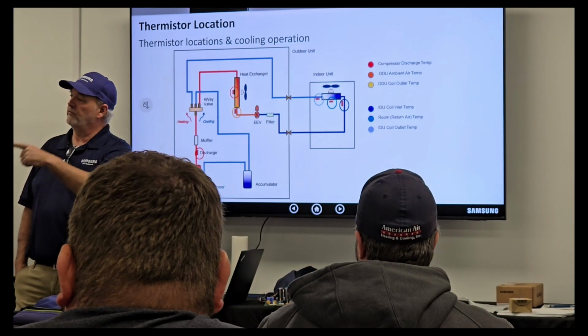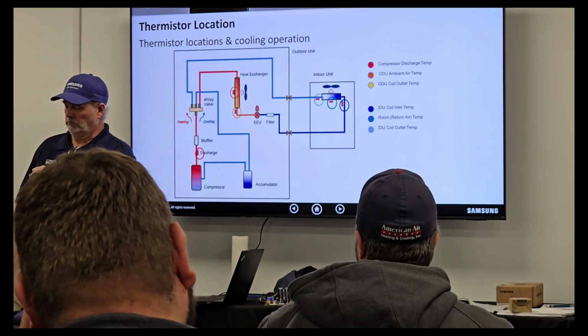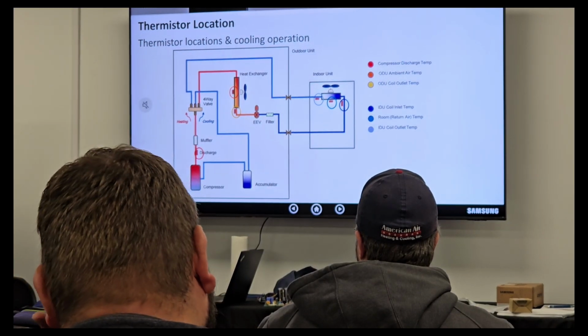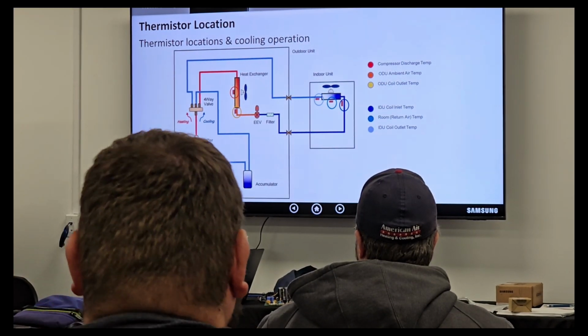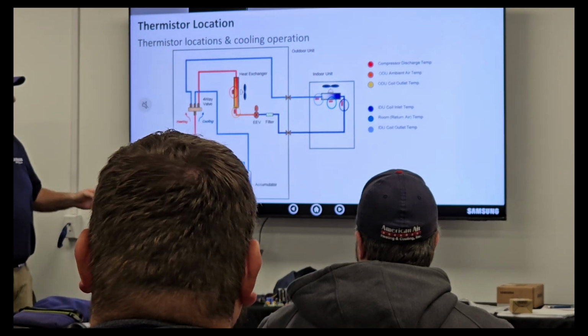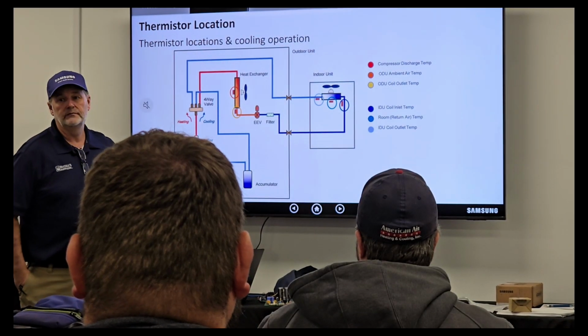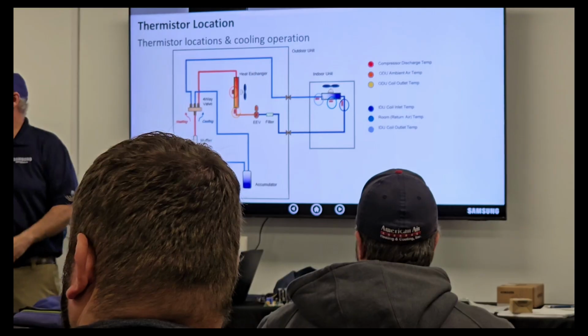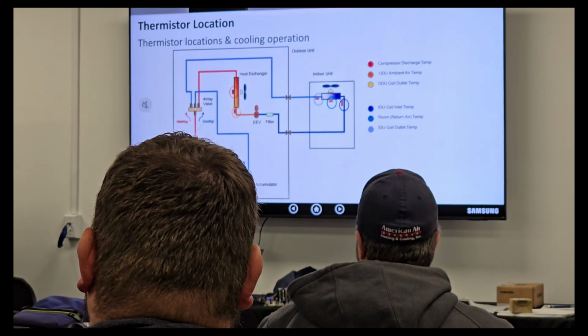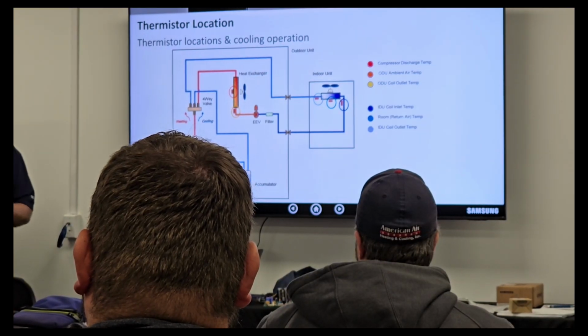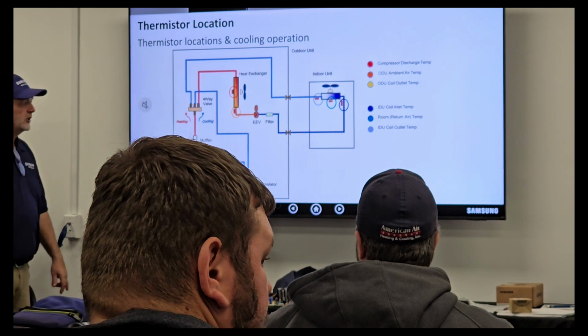From there, all that debris is gonna go straight to the four-way valve, straight to my EEV. Does it cause any problems? Maybe not at first, but what happens to that debris when it gets to that compressor? It destroys the compressor inside. Now we change the oil, we change the color of the oil. There's a lot of stuff that goes on.